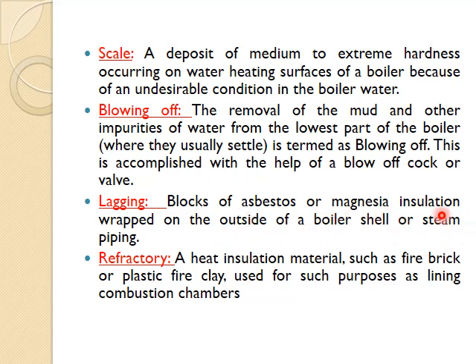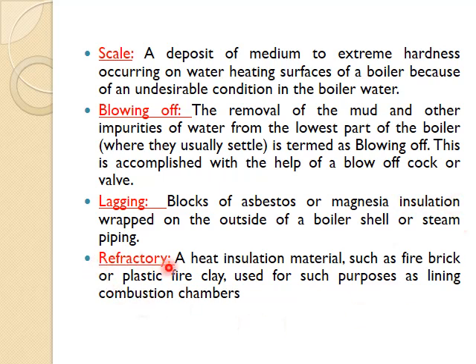Lagging: blocks of asbestos or magnesia insulation wrapped on the outside of the boiler shell or steam piping is called lagging. We need lagging in order to reduce heat leakage from the boiler or steam tubes. Asbestos and magnesia insulations have very low thermal conductance, meaning they are very poor conductors of heat.